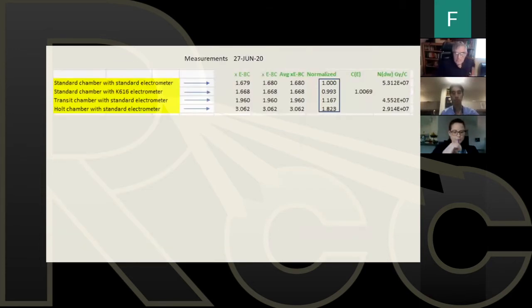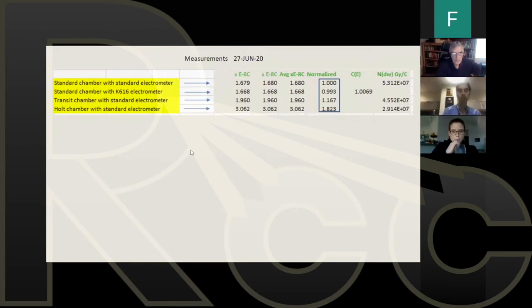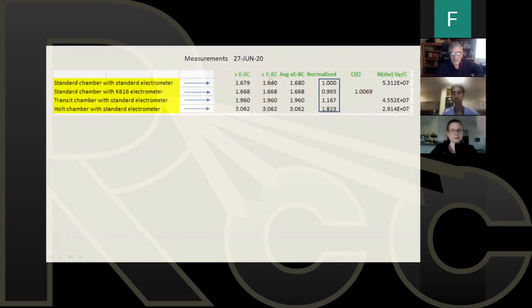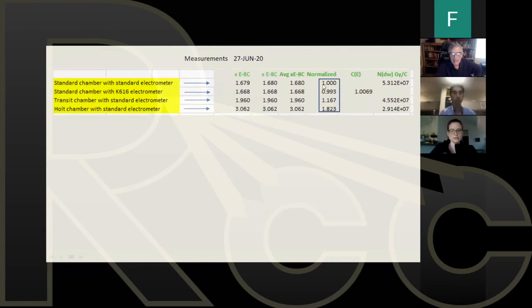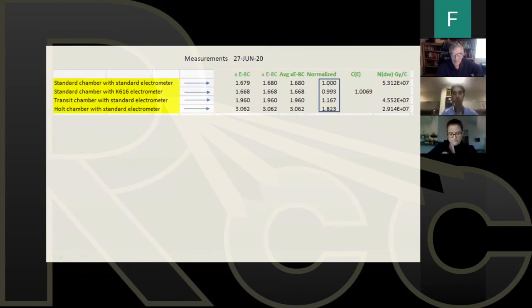Here's a spreadsheet that I use, and it shows you the different readings. The standard chamber with the standard electrometer gives me readings in 10 to the minus 8 coulombs. So this column here shows the average. And since this is my standard, and this is the number, NDW, that I got from my calibration lab, I normalize that value to 1.000. That becomes my standard. Now to that, I compare everything else.